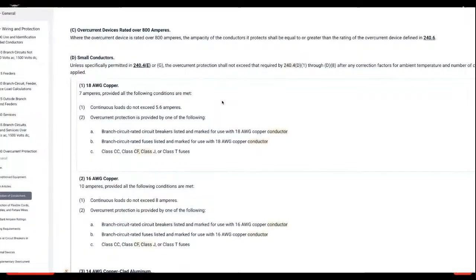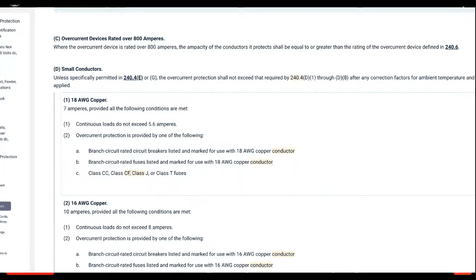Okay. So here's 240.4C. Let's see what it says. Where the overcurrent device is rated over 800 amps, the ampacity of the conductors it protects shall be equal to or greater than the rating of the overcurrent device, defined in 240.6. So if I take 4-aught conductors that are good at 230 amps and I parallel it 4 times, that's 920 amps. Are you saying that I need to put a 1,000 amp overcurrent device here instead of a 900 amp, Jeremy? Because it says the conductors have to be equal to or greater than the rating of the overcurrent device. How would I go up? Yeah. It literally says that.